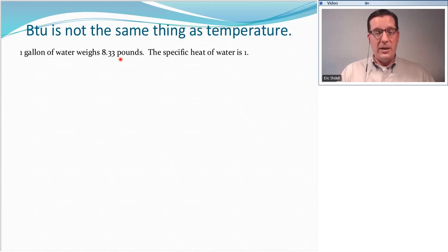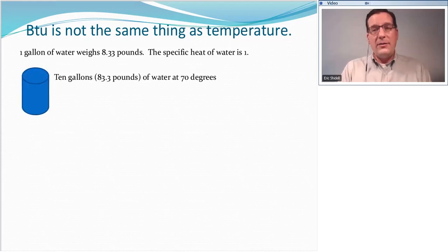The specific heat of water is 1, meaning it takes 1 BTU to raise 1 pound of water 1 degree Fahrenheit. That's the definition of a BTU. It's also the thing known as specific heat. So if I have 10 gallons of water, they're going to weigh 83.3 pounds.